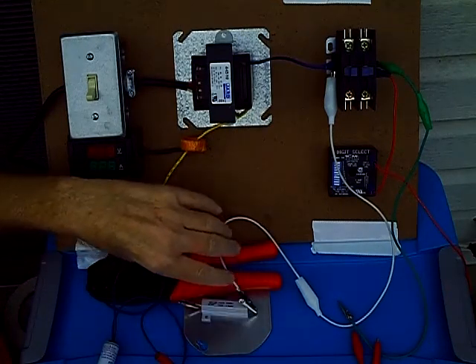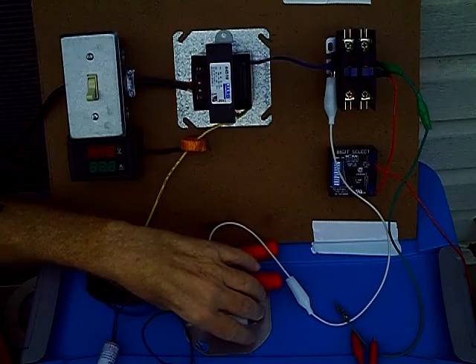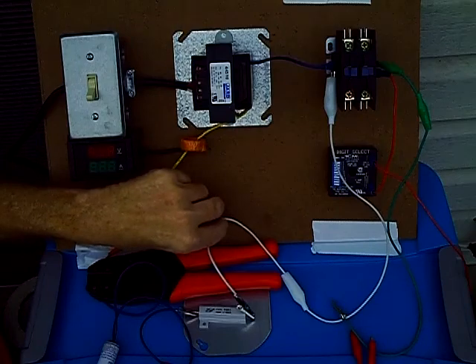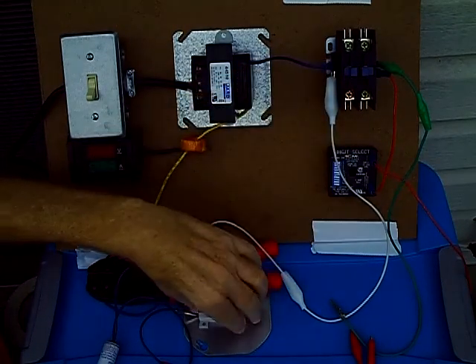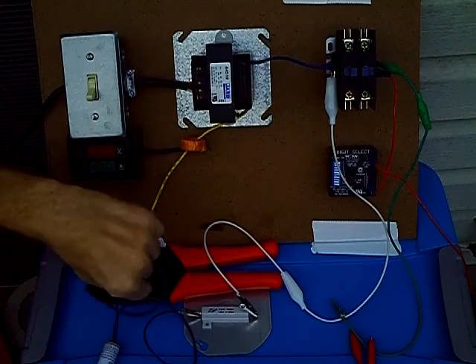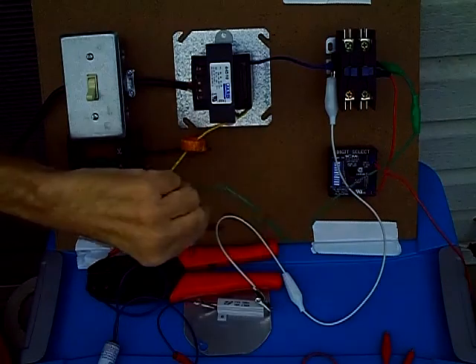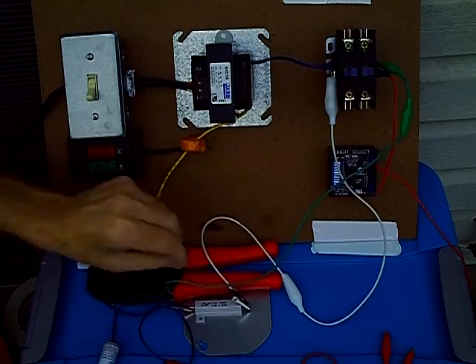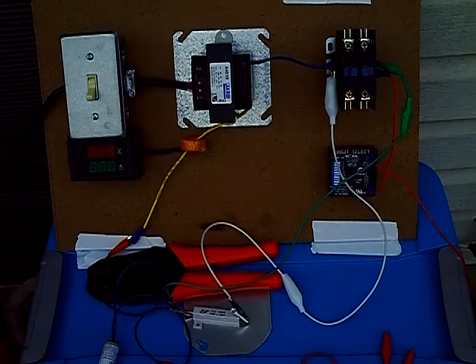That's something the other type of popper or the other types of short locators, they just can't do it. Two amp short or anything that can actually burn up that transformer, it will not find. It has to be a direct short. And I've got this white jumper lead going to one side of this resistor and then the yellow wire coming out of the transformer secondary going through the ShortPro tool and to the other side. And I'm just going to add one more thing to the circuit. What this is doing is also powering up the coil of this contactor and that way I can generate about 1.6 amps or so.